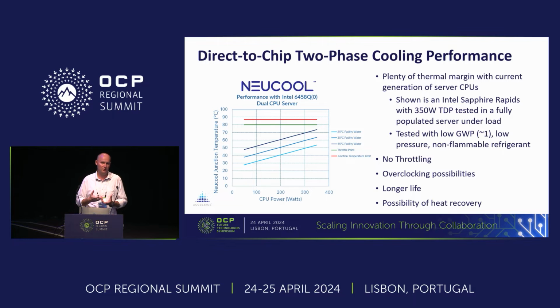What we did here is take a fully populated rack running at a 50 kilowatt total power load, and test actual Intel chips, not test vehicles. These are actual measured junction temperatures on Intel chips for that 2-processor server I showed before, run at 3 different facility water temperatures. To be clear, I'm not showing the temperature of fluid entering the server, but the temperature of the facility water entering the CDU for this rack running at 50 kilowatts.